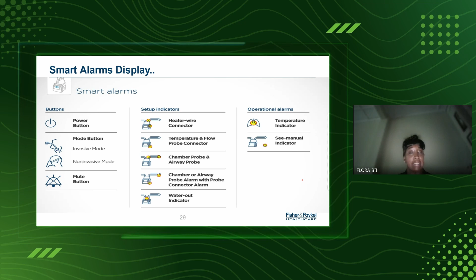we had described earlier. So when you look at best practices, what are we talking about here? You want to check the basics, have the proper setup and use, and also just use manufacturer approved humidification chambers and circuits. Check that you've selected the correct mode. Now, when you select invasive mode, you're basically communicating or requesting the humidifier to provide you with 37 degrees centigrade and 44 milligrams of humidity. When it's on mask mode, it would reduce that temperature to about 31 degrees centigrade, just in line with the skin temperature on the face.